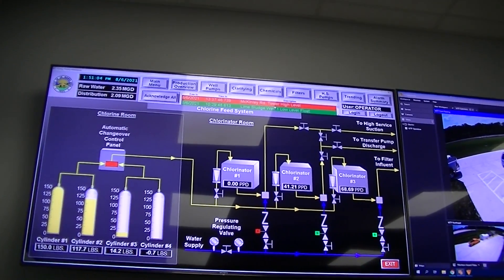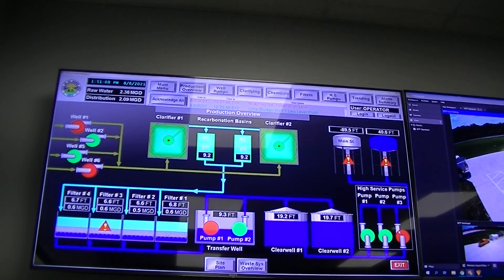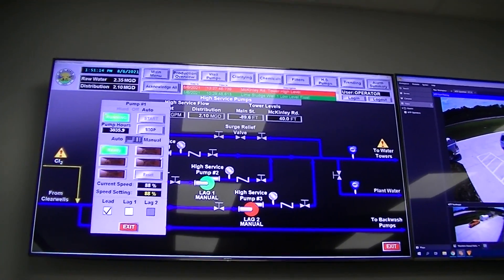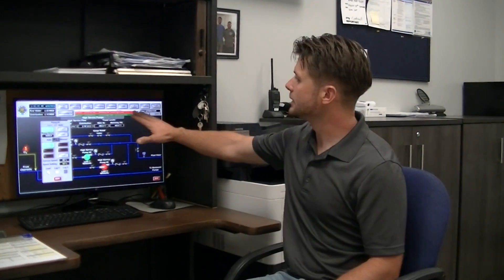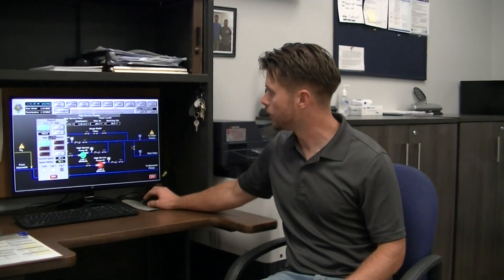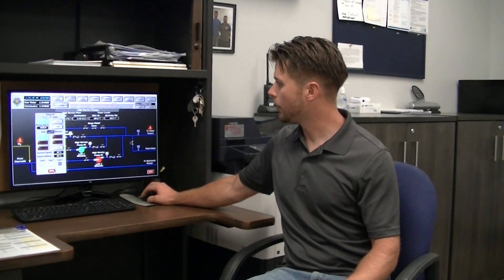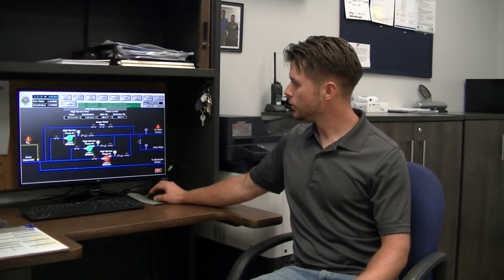So there's an alarm that just went out. If you were sitting in here, how would you know that? We have remote access to SCADA on the cell phone. A lot of times if it's a major issue, it will notify the phone — we call it a Win 911 call. The recording robot sends you a message. This isn't a major issue, so this won't get transferred to the phone. This is just telling us our tower level is getting pretty high, so I'm going to turn the high service pump off so we don't overflow the tower. And it's as easy as push a button — then you'll see it go red.